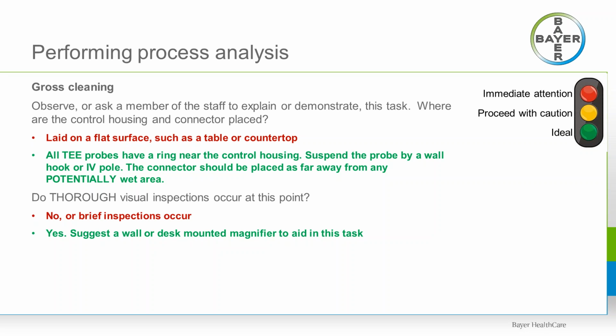So it's the top 6 inches of the probe that really needs to be examined for any area that would even potentially permit any type of fluid invasion. If any area is identified that you might think will let fluid in, the probe should really be removed from service for further inspection. When in doubt, it's always best to err on the side of caution. We've even had some customers use a wall-mounted or gooseneck magnifier to help the cleaning personnel in this task.